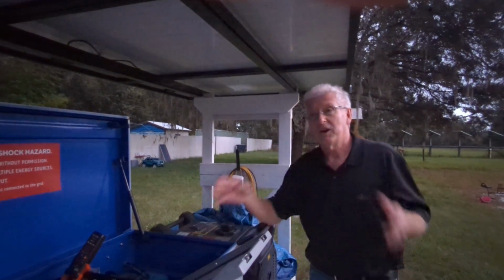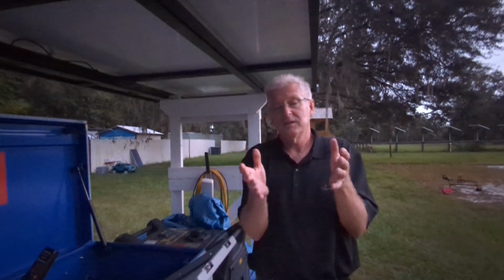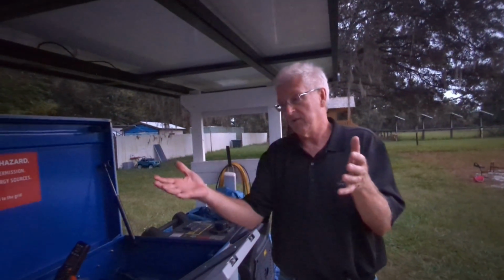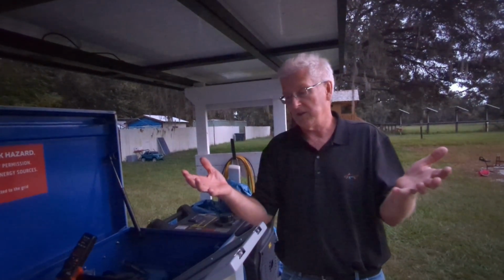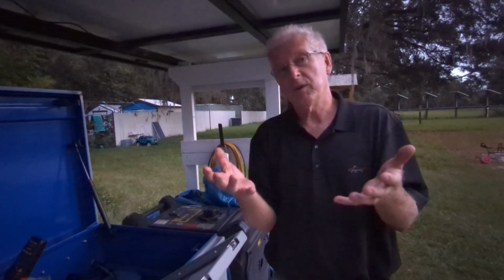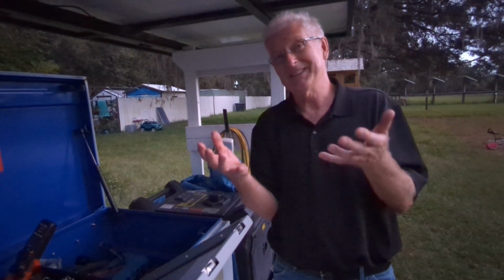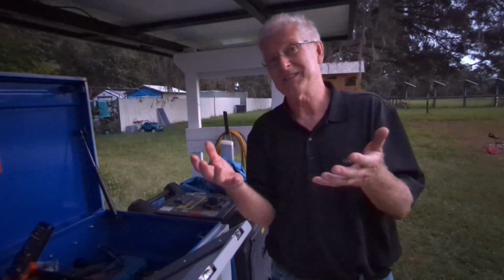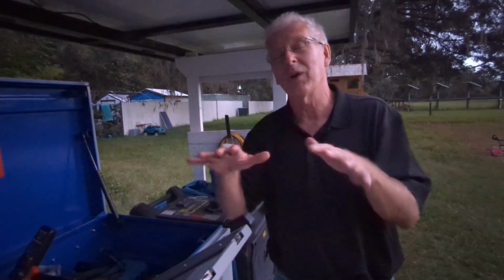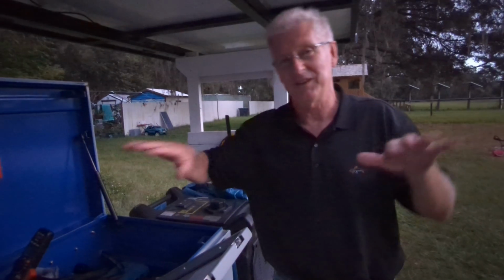So what the auto transformer basically does is take all the load you have on one leg, all the load you have on the other leg, and balance those two so that they're even. So the inverter will continue to operate without failure as long as the load doesn't exceed 5, and that 5 is the sum of the two, without worrying about the threshold on either leg, 2.5 on either. Right, it balances them down.